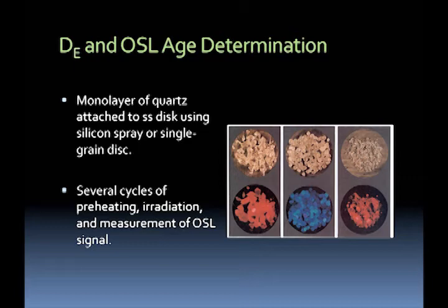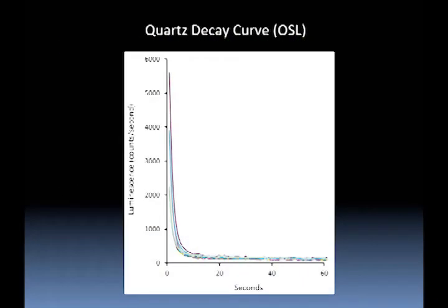So the measurement doesn't take that long. We need to replicate the burial dose of radiation. So we have to dose that sample. If your sample is 10,000 years old, we need to give it 10,000 years of radiation. Luckily, we don't have to wait 10,000 years, but we still have to wait on the order of hours to days to replicate that dose. So a typical sample will take 1 week of dedicated instrument time. I have 2 machines, so I can get about 110 samples done a year. So that's where our time comes in.